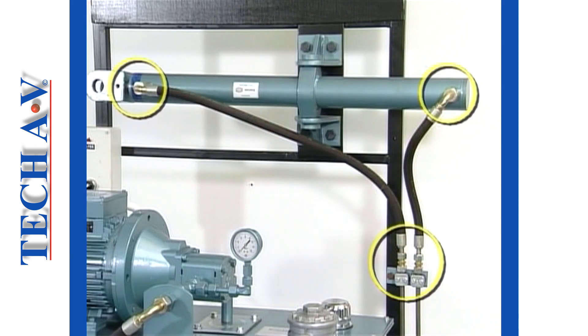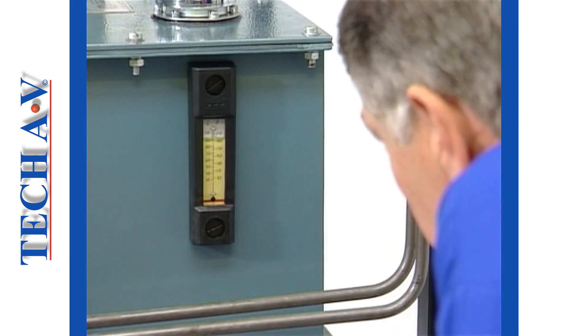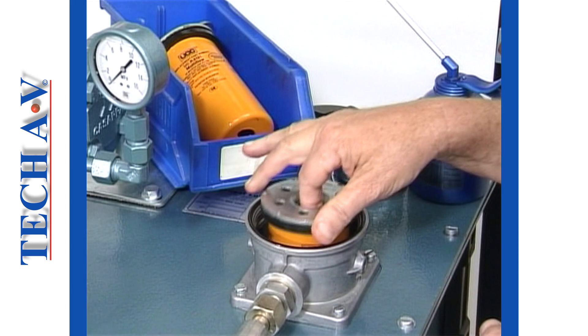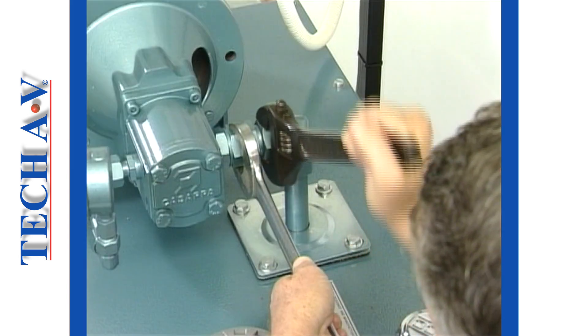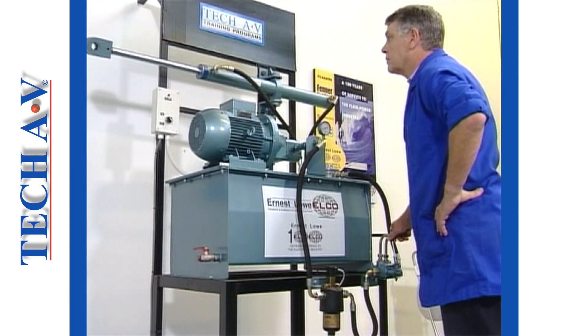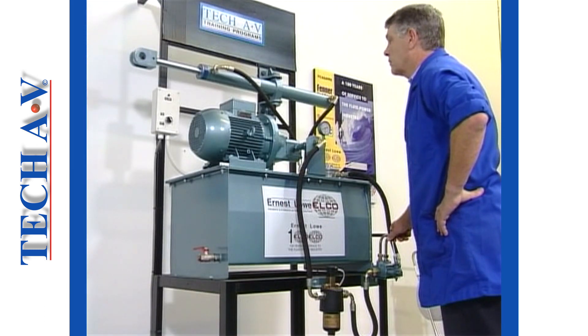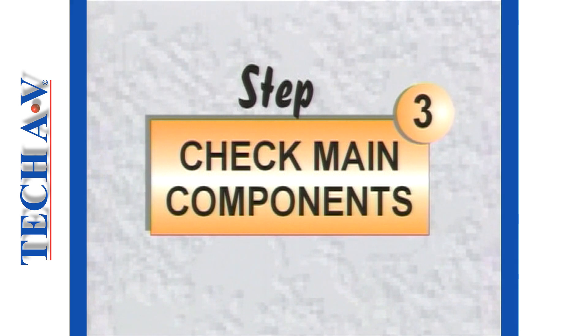The working line connections should be checked for leaks and secured if necessary. Once you have made the necessary normalizing checks and effected any corrections, and the system is still displaying a fault, then you must move to step 3 — that is, you must check the major system components.